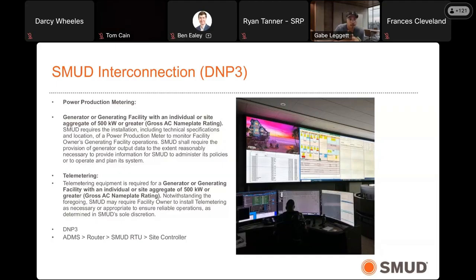Right now at SMUD, if we have a generation facility, usually solar or a battery system greater than 500 kilowatts, that requires a power production meter, and that requires it to be incorporated into our SCADA network for the ability for curtailment as well as monitoring and control.